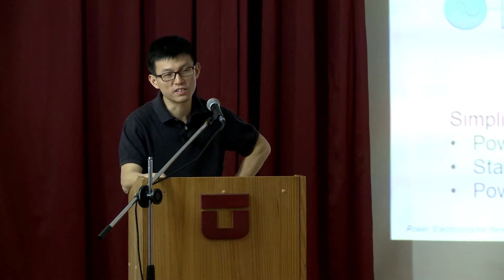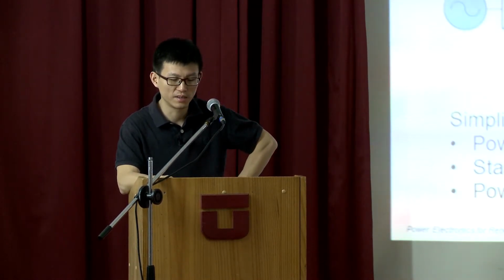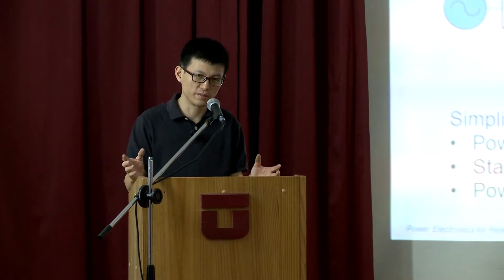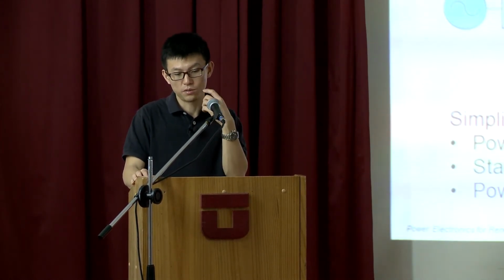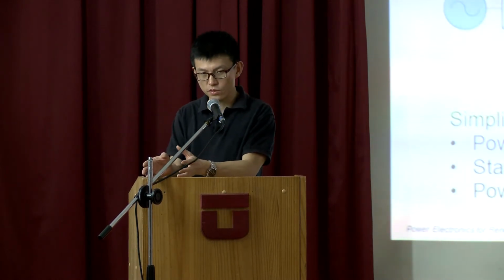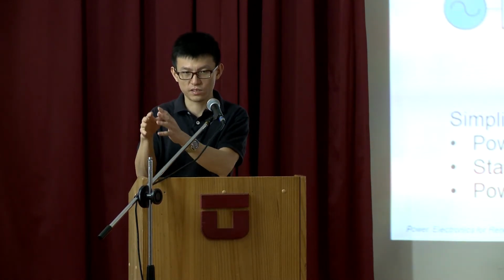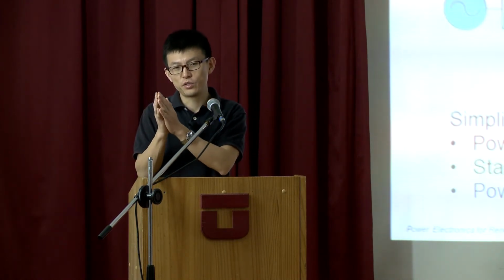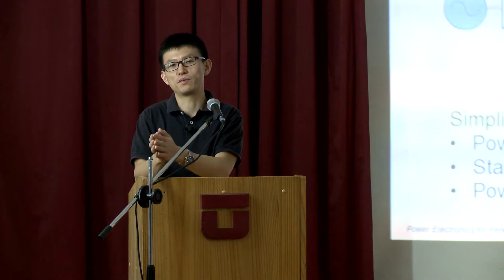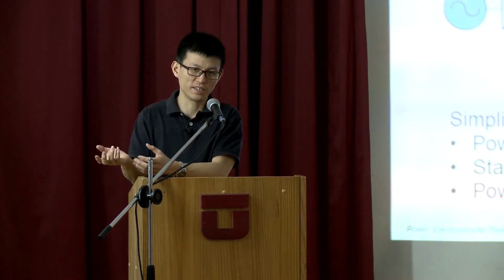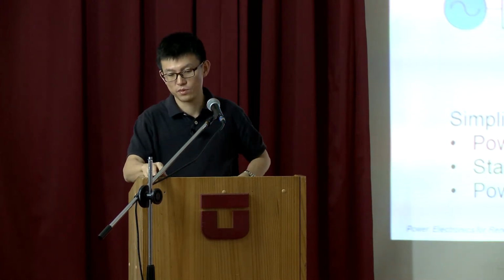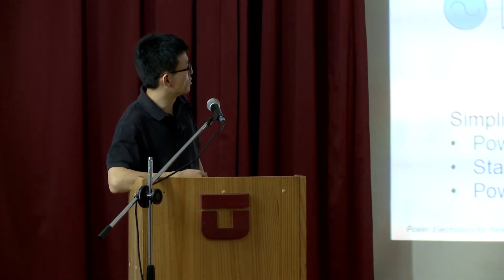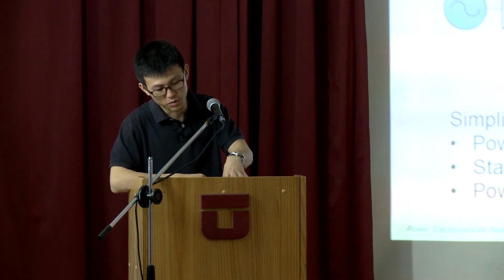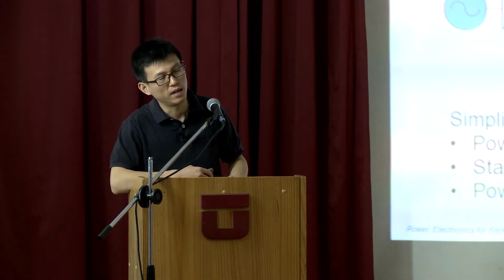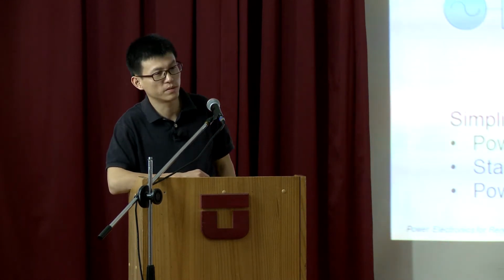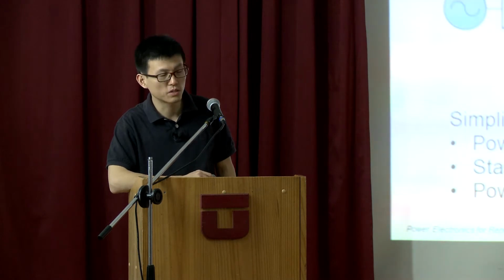These constant power loads have more impact on system stability because of the negative impedance. One method is to look locally and change the dynamics of these local constant power loads, which means you still have negative impedance, but probably its impact is lower. At the system level, you have to be more careful, because this can shift all the system poles to the right-hand plane. In Clean Sky 1 we actually developed a stability analysis tool for this.